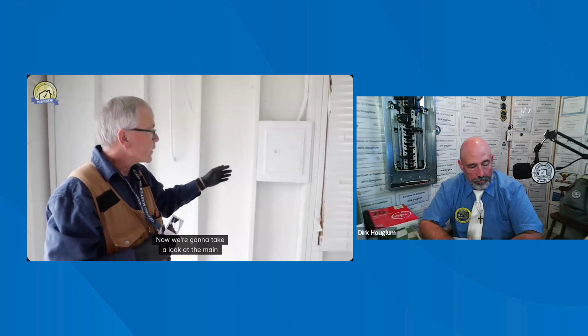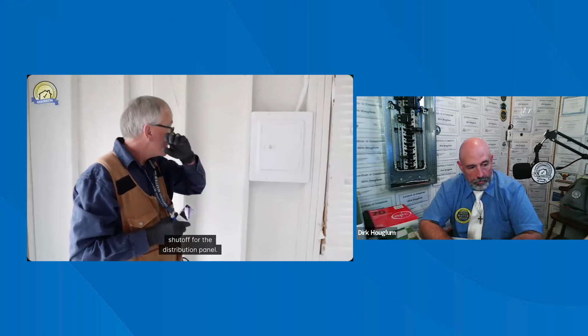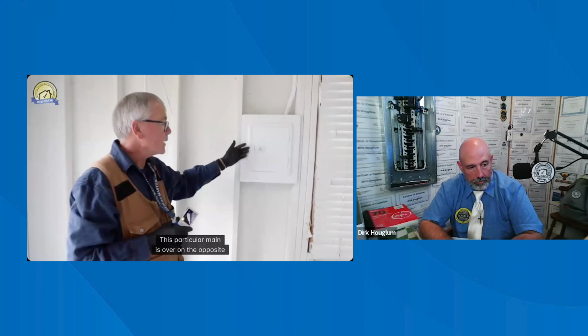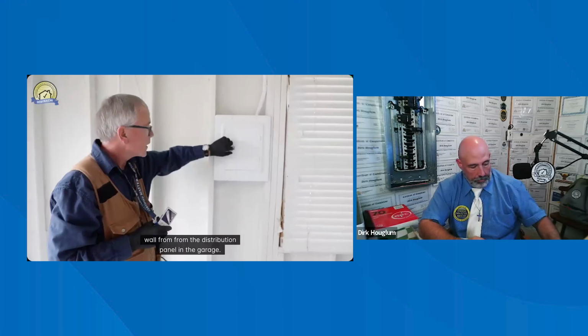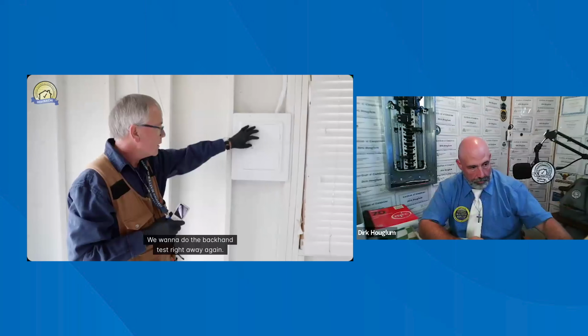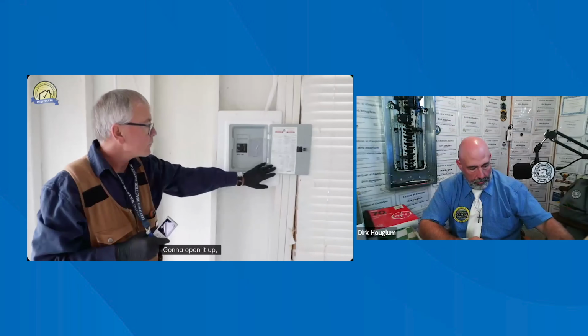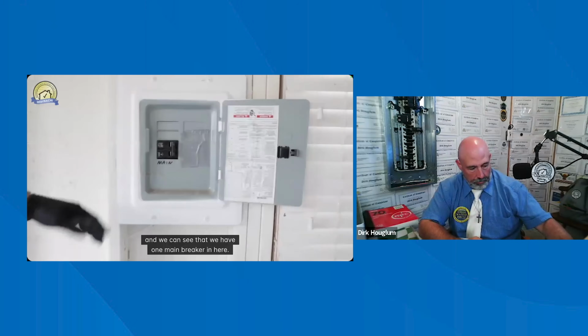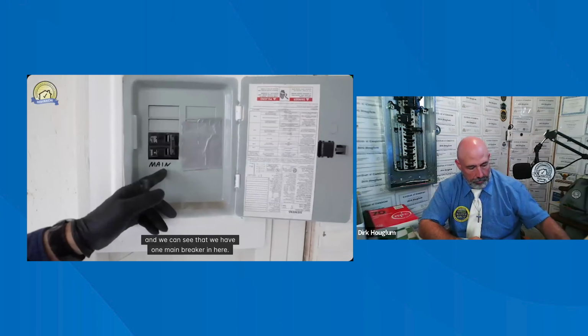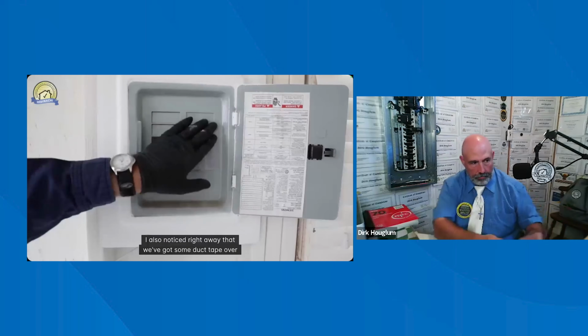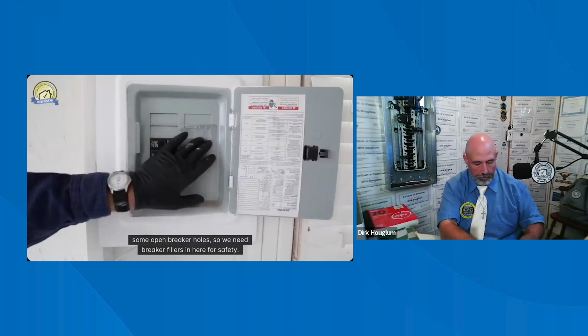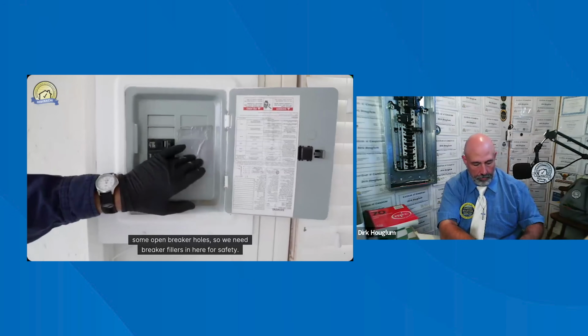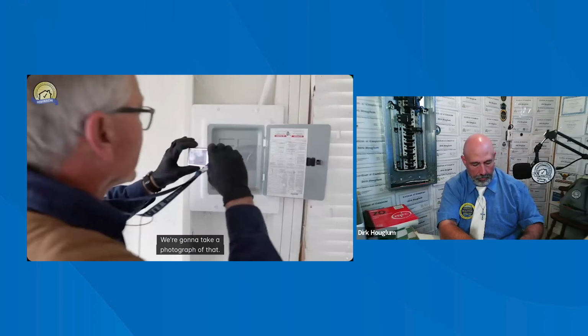Okay, now we're going to take a look at the main shutoff for the distribution panel. This particular main is over on the opposite wall from the distribution panel in the garage. We want to do the backhand test right away again. I'm going to open it up, and we can see that we have one main breaker in here. I also noticed right away that we've got some duct tape over some open breaker holes. So we need breaker fillers in here for safety. We're going to take a photograph of that.